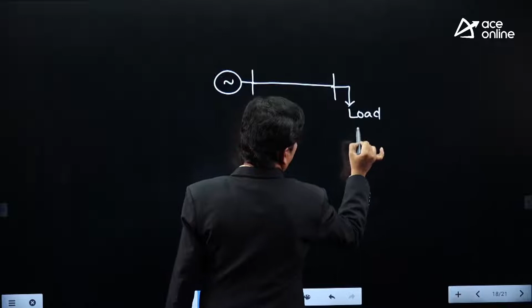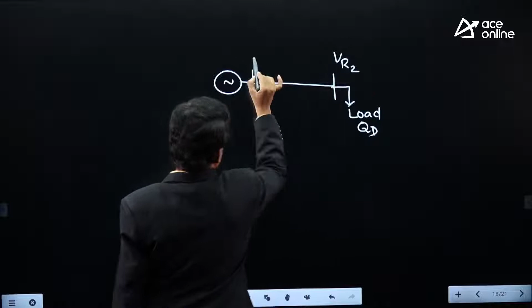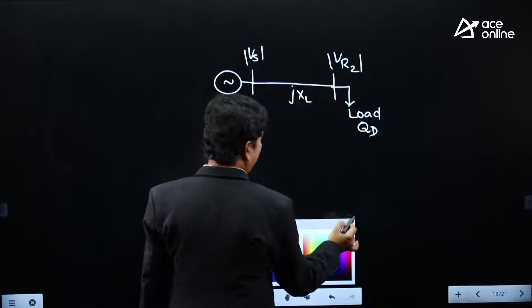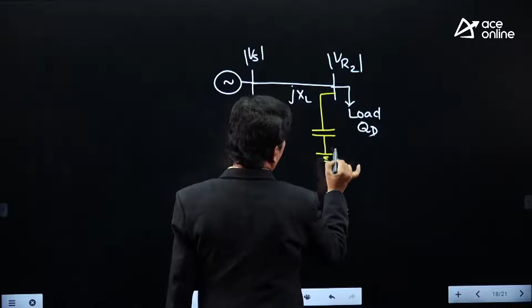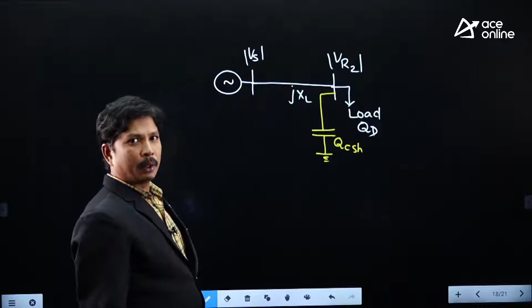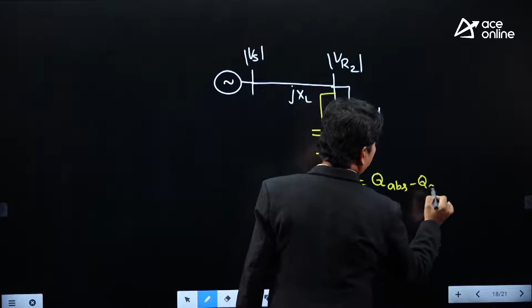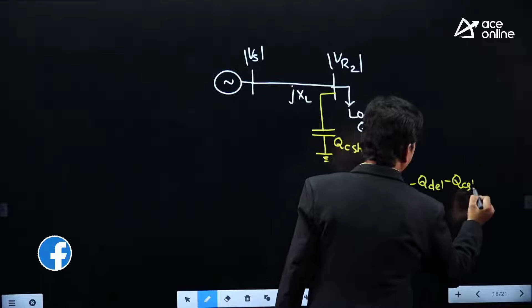Clear? So now we'll connect a shunt capacitor at the load side. Now check here. This is the system we are having. Here we are having the load, which is having a Q demand, receiving end voltage VR2 magnitude, sending end voltage Vs, line reactance jXL. Now here we are connecting a capacitor of QC. We can call it QCSH, the shunt capacitor value. Therefore the overall reactive power demand will become QD is equivalent to Q absorbed minus Q delivered of the load, and extra we are having minus QCSH.